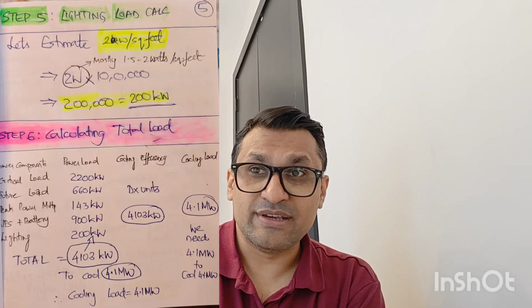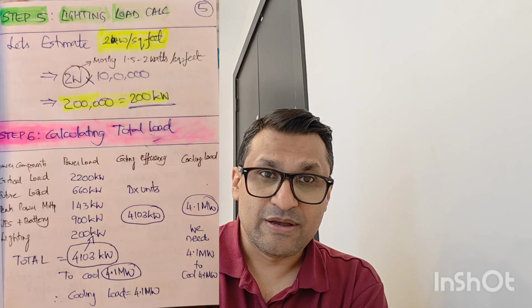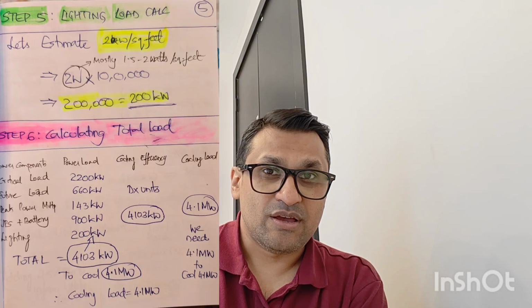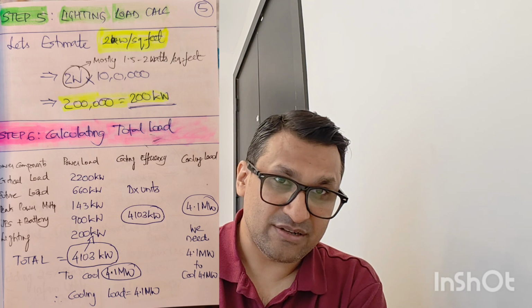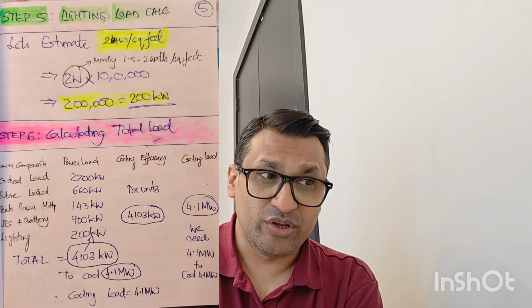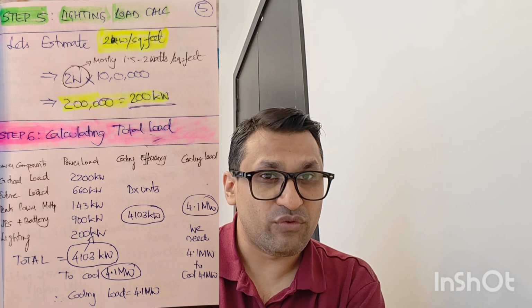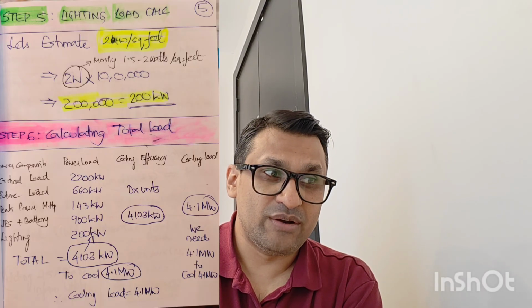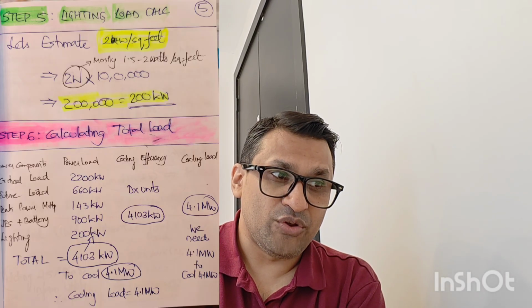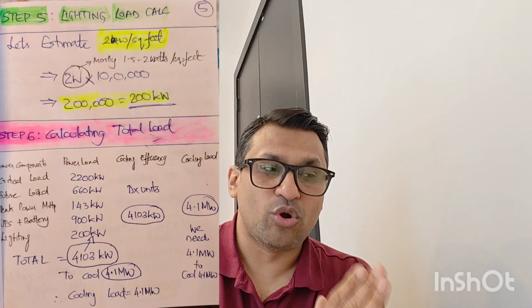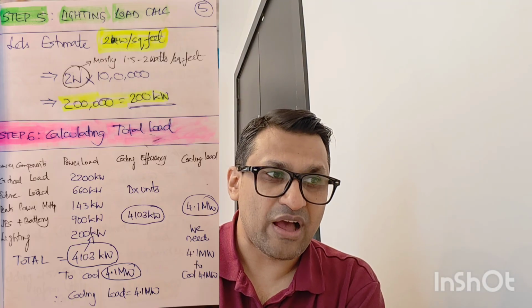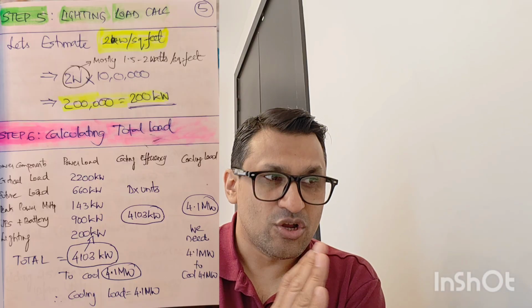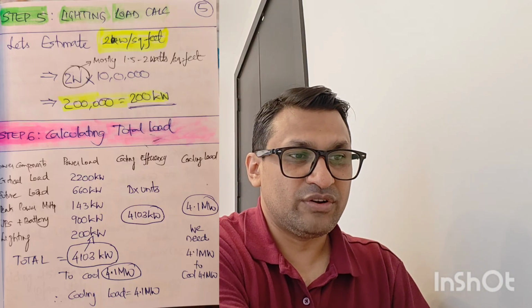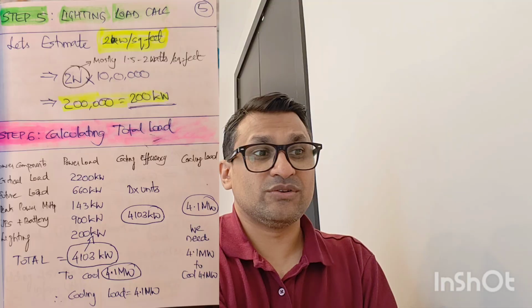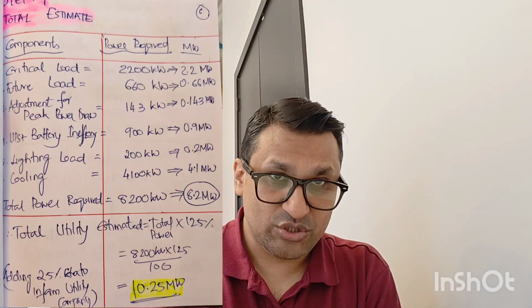So the cooling efficiency, now we're considering 100% DX systems. It's just for design purposes. We could use 50% chilled water, then the design considerations change. Because for cooling DX units, cooling efficiency is 1, so you need 4103 kilowatt or 4.1 megawatt. So you need to have a cooling capacity of 4.1 megawatt to cool 4.1 megawatt of the load. Okay, so at least we figured out the cooling load and the amount of cooling required to cool down the total load.